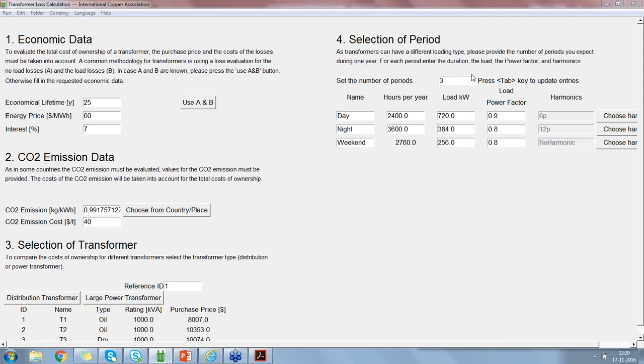In this example, you can mention as many periods as you want. We are looking at 1 year, so that means 8,760 hours. And you can make a lot of periods if you want to. In this example, I've shown you 3. I said, okay, this transformer is used during daylight for a couple of hours per year, during night and during the weekends it's a little bit less loaded or whatever. You can fill in the number of hours, and also you can set the loading of the transformer, as long as the loading is not larger than the rating which you have given in section 3. Also, in case you want to use the power factor, feel free to adapt.